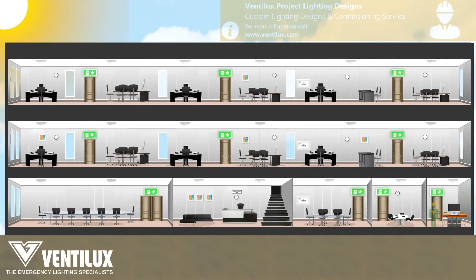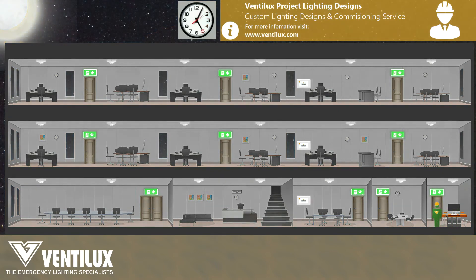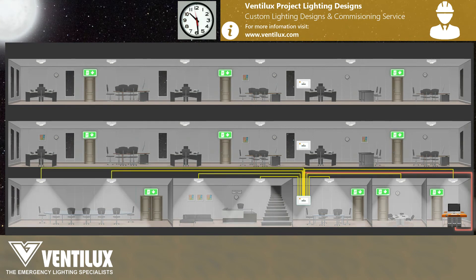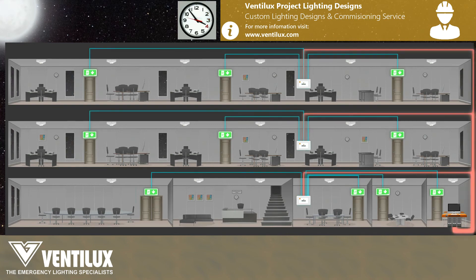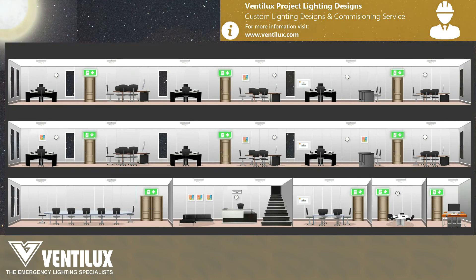With the DALI system integrated on site, the maintenance engineer can perform a wide variety of different tests from a single, centralized location or in any area of the building by simply using the DALI controller panel assigned to that specific zone. Isolating any or all luminaires connected to that DALI controller, an automated testing procedure can be programmed to be carried out at a specific time. Upon completion, testing reports will be sent back by each individual luminaire to the DALI controller. The entire emergency lighting testing of a building can be carried out from the centralized location and programmed to automatically test overnight, as not to disrupt the daily work routines, making the requirement of emergency lighting testing effortless, time and cost efficient.